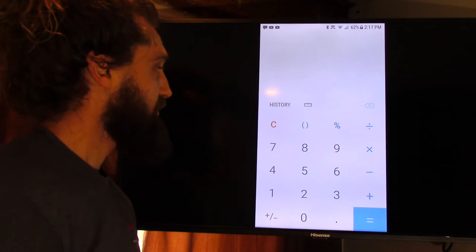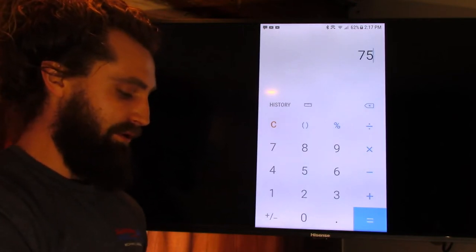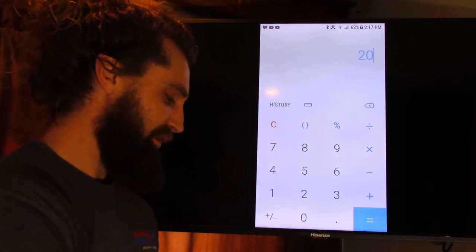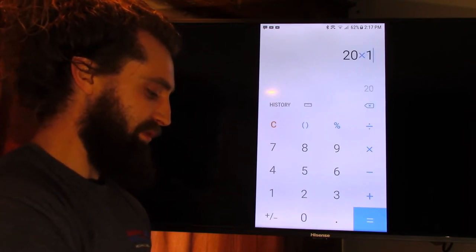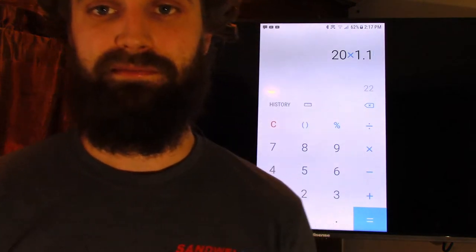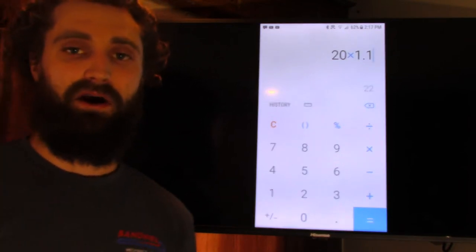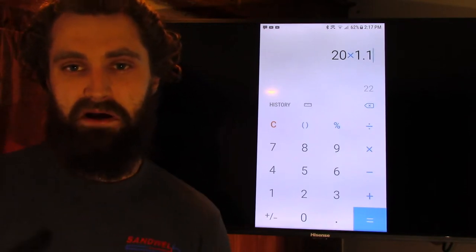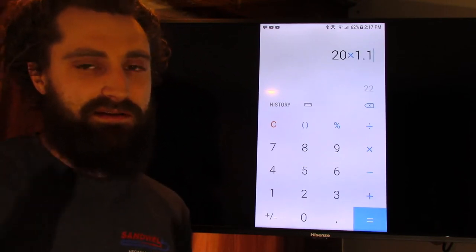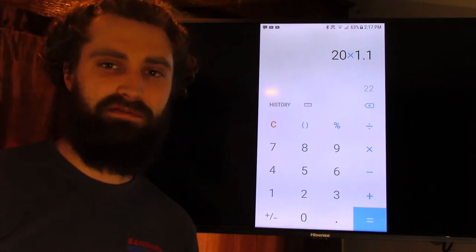So let's just run through this example here. We had 75 degrees on our return minus our 55 degrees on our supply. That's a 20 degree drop, right? Good. Now, we're going to multiply that times our 1.1, which is our constant. Now, here's the tricky part, because you've got to go to the supply house and get another tool, and that is an anemometer of some sort. You've got to know how much air is going through that system. You're not going to the blower motor and saying, it's on medium speed, I think it's 800 CFM, or it's on high, we're going to try 1200, or it's a 4-ton unit times 400 CFM per ton. So that gives me 1600 CFM. Yeah, that's what it is.